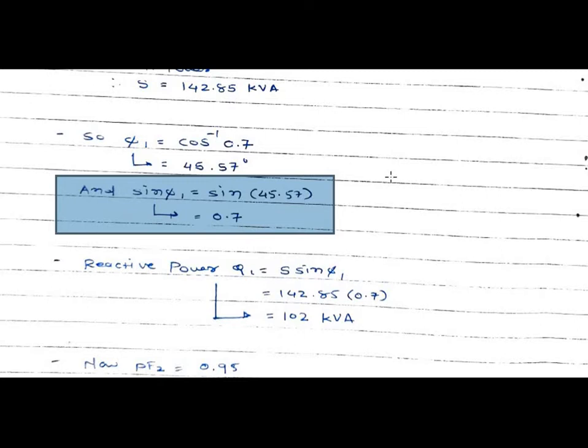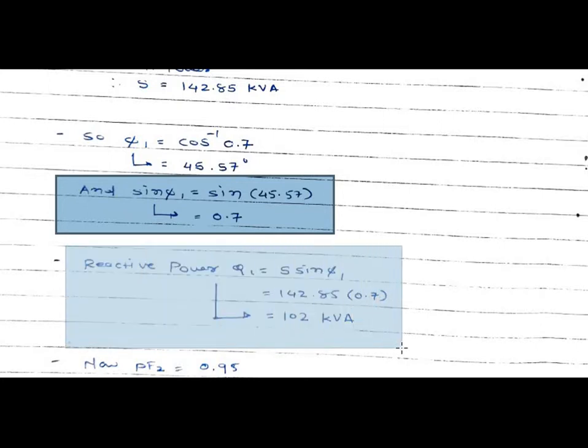Reactive power Q1 is equal to S times sine phi 1. This is the reactive power corresponding to the power factor of 0.7. Putting the values of S and sine phi 1 into this equation, we get 142.85 multiplied by 0.7. The value of reactive power Q1 is given by 102 KVAR.